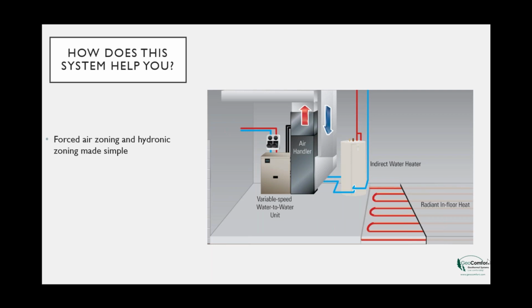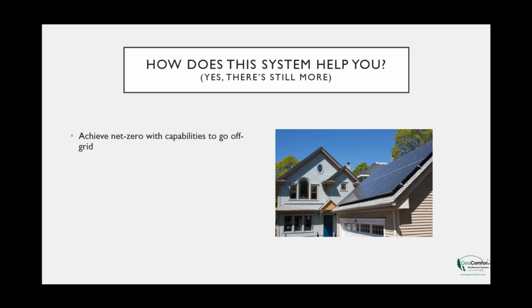We can also do forced air. And the great thing about this product is we can have multiple zones within the home. So now we can condition the areas where you're living, and the other zones where you're not, you can turn down or set back. And it can do all of that through a ducted system. Obviously for cooling, we're doing a ducted system. We can also do ductless, but we can have multiple zones on the forced air, multiple zones on the radiant floor, and do the domestic hot water all in this compact, all-in-one variable speed system. So it's very, very flexible in what we can design into the home.